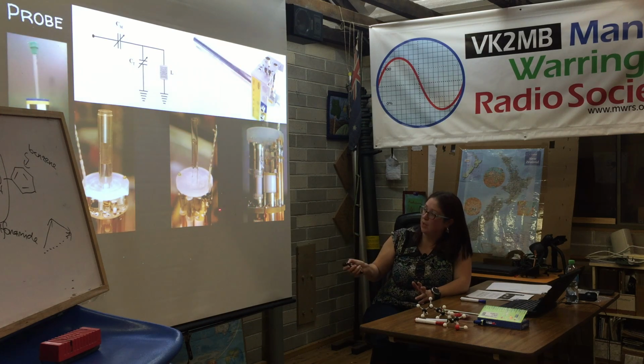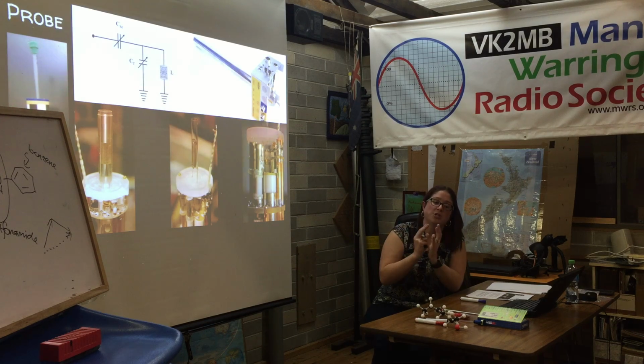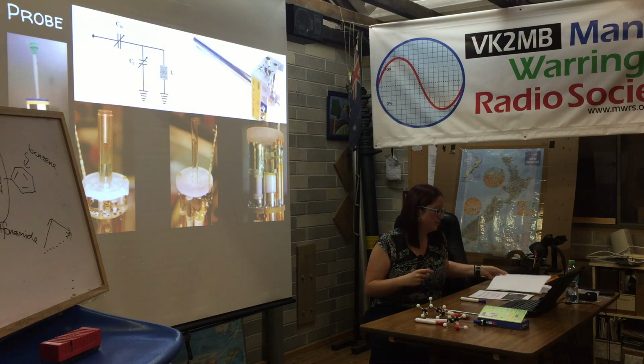This is a blow up of what's happening down below, and this saddle coil was sitting on top of this Helmholtz. So you often have two observed coils. Typically you would have at least two. The outer coil would be used to observe the high frequency, high sensitivity nuclei like proton or fluorine. And this inner coil, which is much closer to the sample, would be used to observe so-called heteronuclei like carbon or nitrogen. We want it to be as close as possible to the sample to get the best signal to noise.